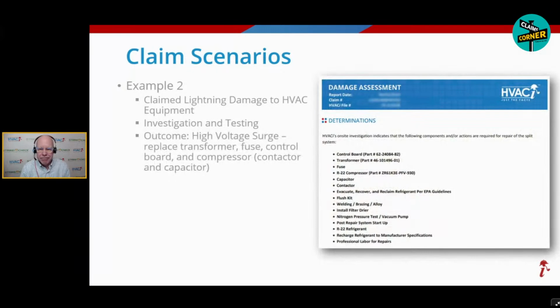We're going to repair this system. 2001 R22 system, and we're going to put in a transformer, a fuse, a control board, and a compressor, including the contactor and capacitor, which are called start components. We have the part numbers, we know the price. You can see we can get the refrigerant and that R22 compressor for a 2001 unit. So perfect proof right there. It can be done. We do it all the time.